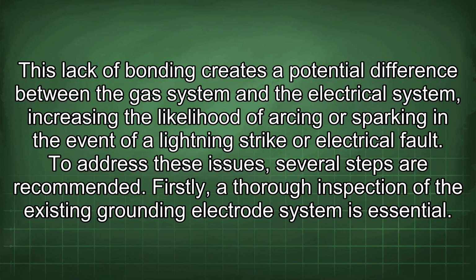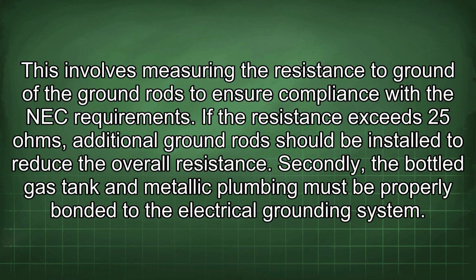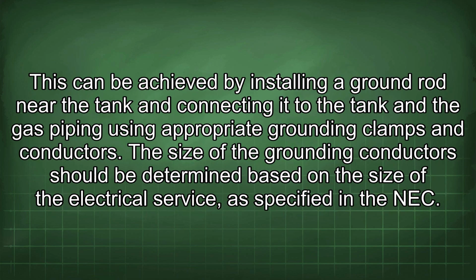Firstly, a thorough inspection of the existing grounding electrode system is essential. This involves measuring the resistance to ground of the ground rods to ensure compliance with the NEC requirements. If the resistance exceeds 25 ohms, additional ground rods should be installed to reduce the overall resistance. Secondly, the bottled gas tank and metallic plumbing must be properly bonded to the electrical grounding system. This can be achieved by installing a ground rod near the tank and connecting it to the tank and the gas piping using appropriate grounding clamps and conductors.